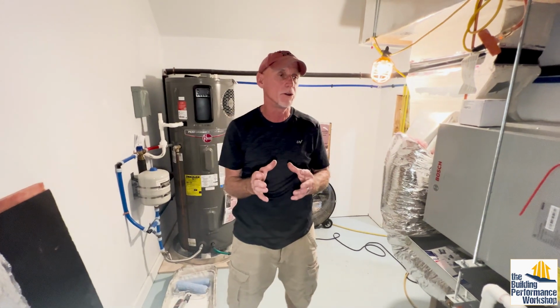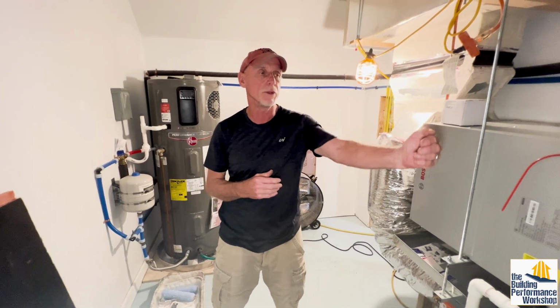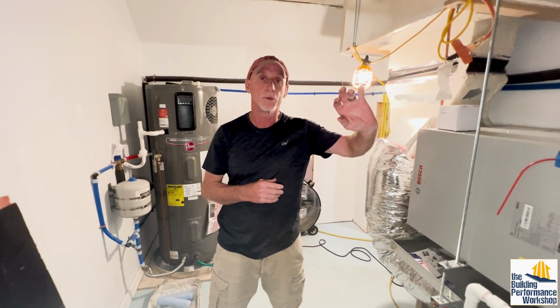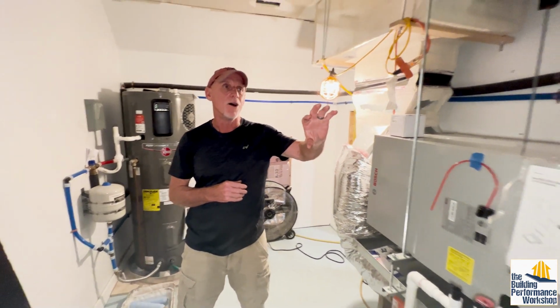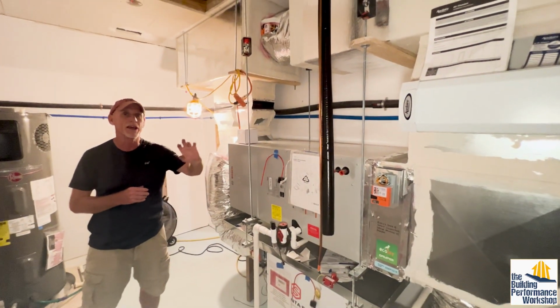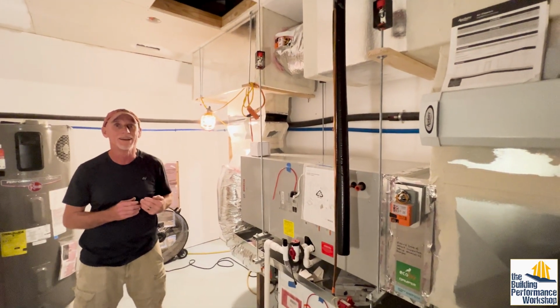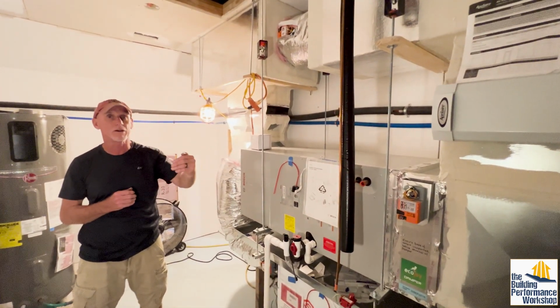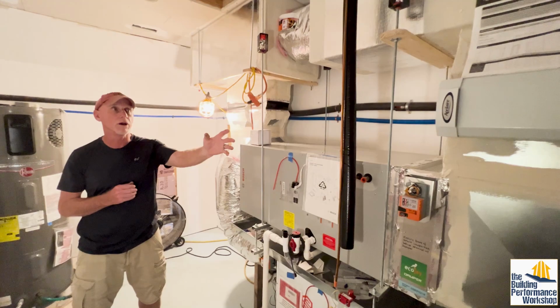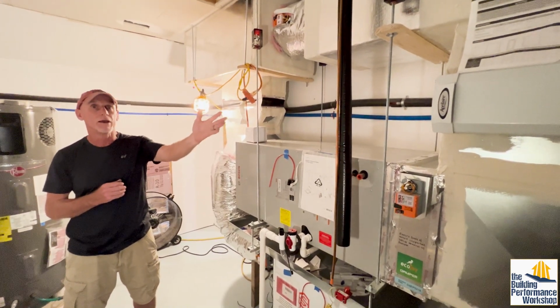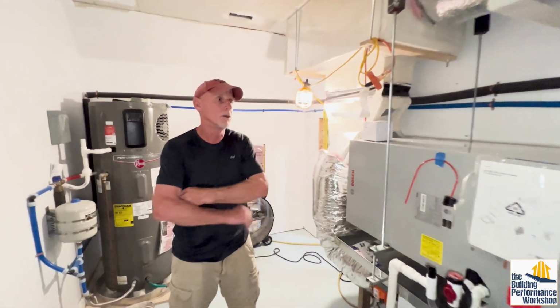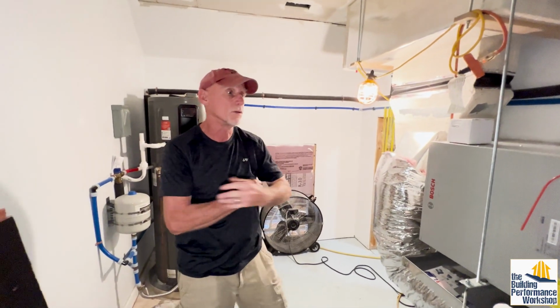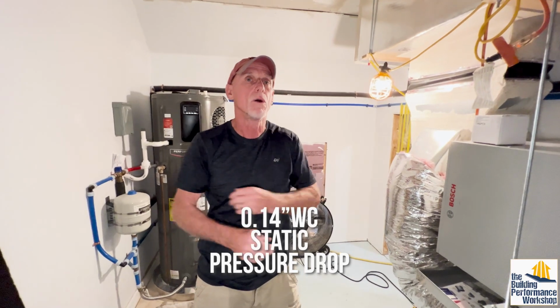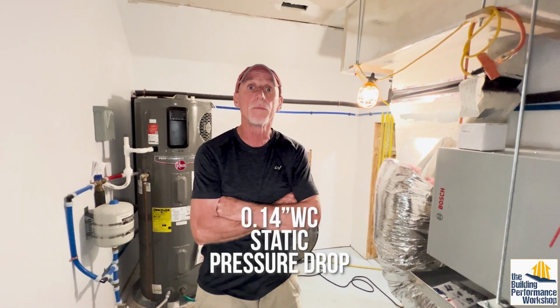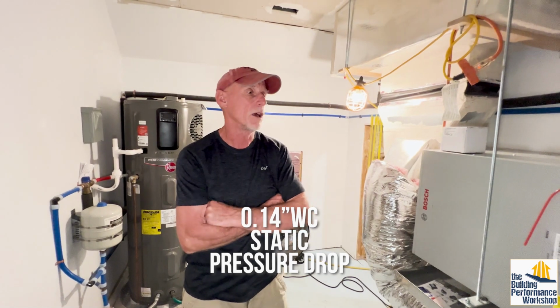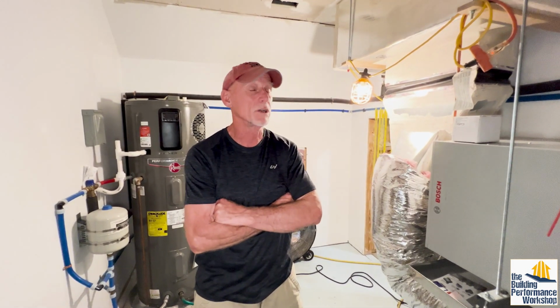One of the things you've mentioned on your shows before is to pick as large a filter as possible for the AHU. I applied that, but there's also a scale to think about - how much the filters cost. So I went as large as I could within a reasonable budget. This is a way larger filter than would normally be required - that's a 20 by 25, I think. Yes. That gave about 0.14 inches water column in static pressure, so I felt that was close enough to where I wanted to be.